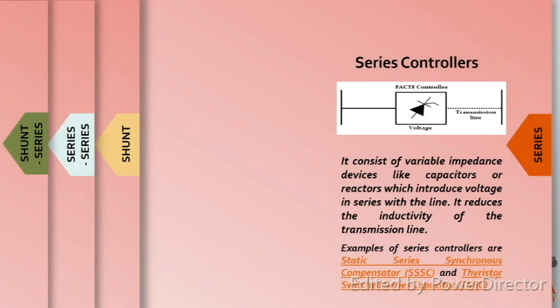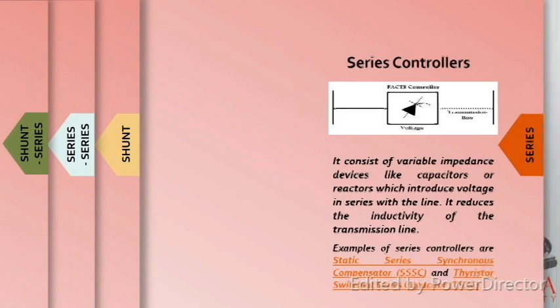There are four main types of FACTS controllers. First is the series controllers. It consists of variable impedance devices like capacitors or reactors, which introduce voltage in series with the line. It reduces the inductivity of the transmission lines. Examples of the series controllers are static synchronous series compensator or SSSC and thyristor switched series capacitor or TSSC, which are widely used in asset optimization, angle stability, and transmission cost minimization.